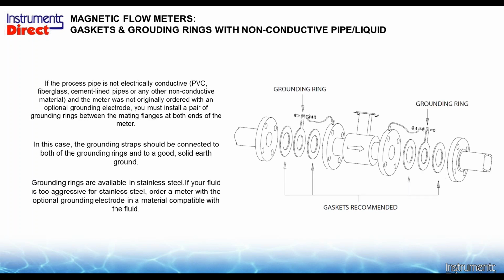Should you have an application with a non-conductive pipe material, such as plastic, PVC, fiberglass, or in some cases cement-lined pipes, then it's probably a good idea to add a grounding ring to the application. In that case, for the installation, we'll have the meter and your mating flange. We use the grounding ring or paddle and put a gasket in between the two, and you can hook up the grounding ring to the mag meter itself.